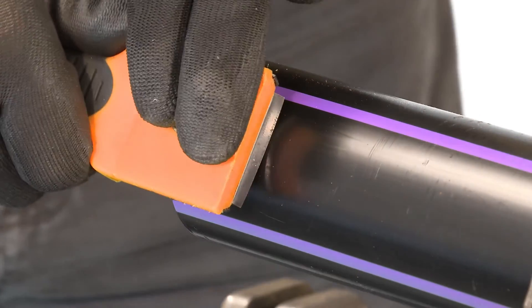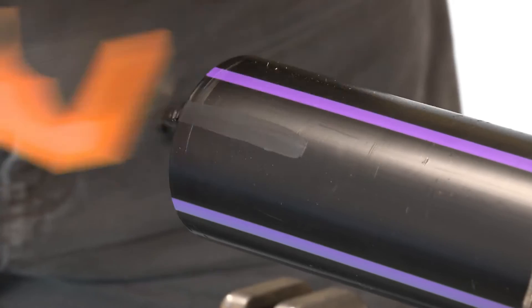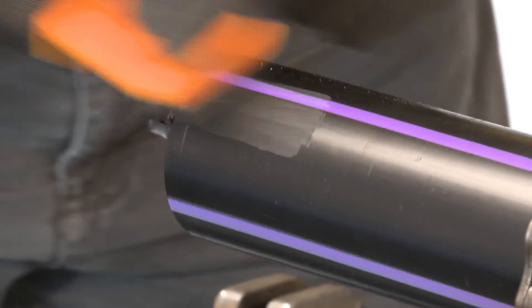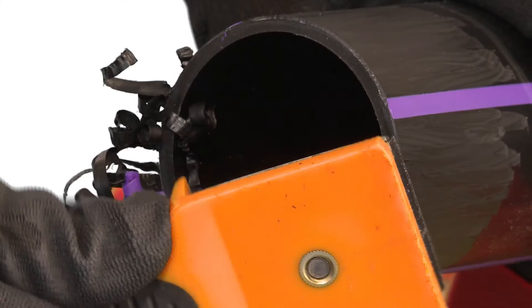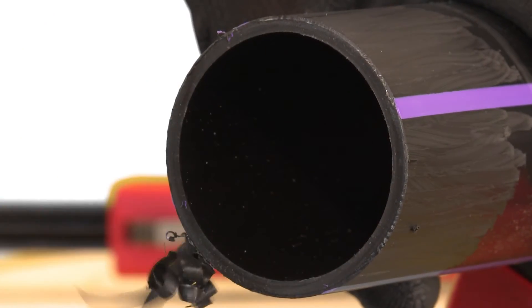Scrape the end of the pipe equivalent to 1.5 times the depth of the socket. This is to show that the pipe has been scraped when inspecting the system prior to leak testing. Once again, ensure that all swarf is removed.